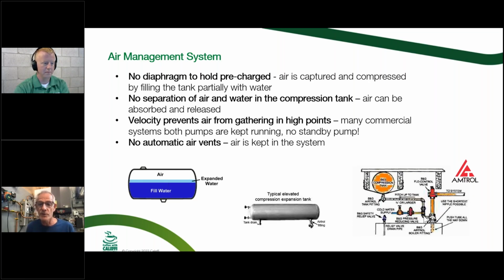So basically what we want to do is, as we take the air out of the top of the boiler, the hot part of the boiler, we want to shove that air bubble up into the top of the tank. That little fitting there is going to have a little tube in it that'll take the air bubble out, and that'll also prevent thermal siphoning, because we don't want the heat from the boiler going up to the tank and just warming up that tank, because then, like I said, we're just losing some heat through the wall of the tank.